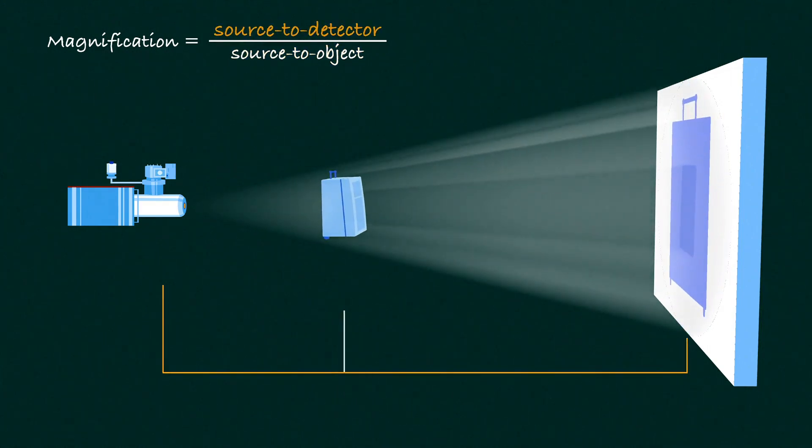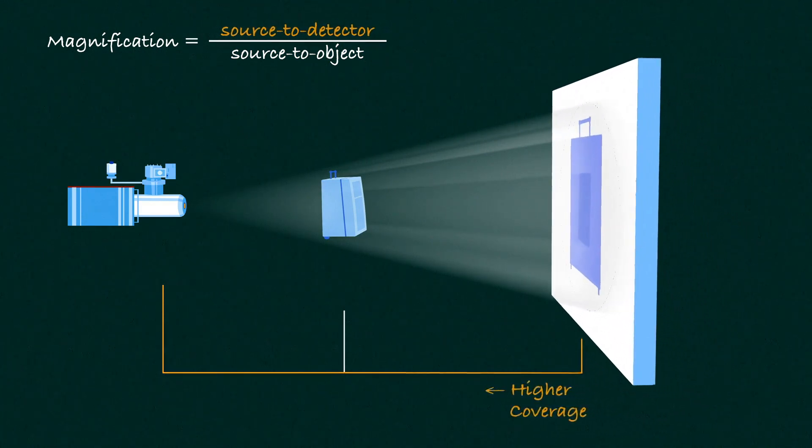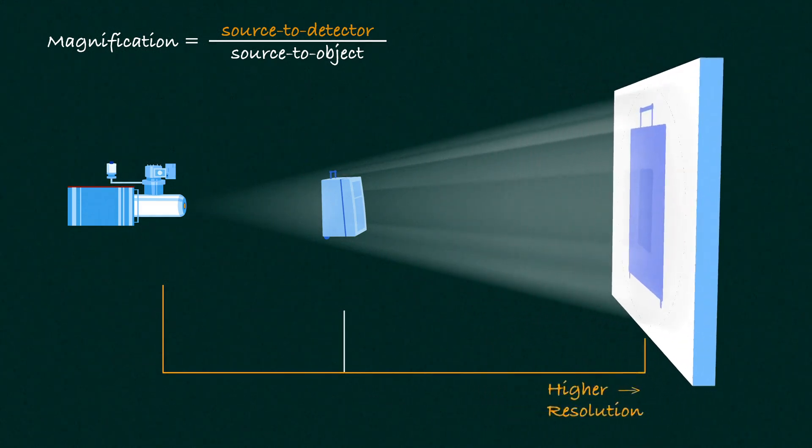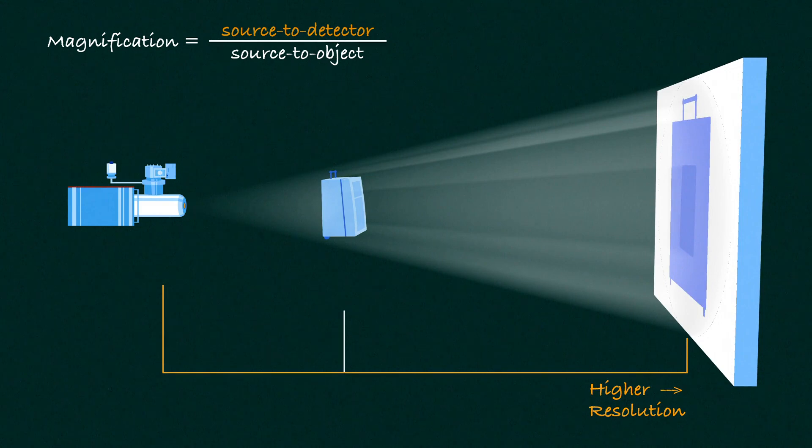The source-to-detector distance also plays a pivotal role in balancing magnification and coverage. Moving the detector closer to the object results in higher coverage, while moving the detector further away yields higher resolution.